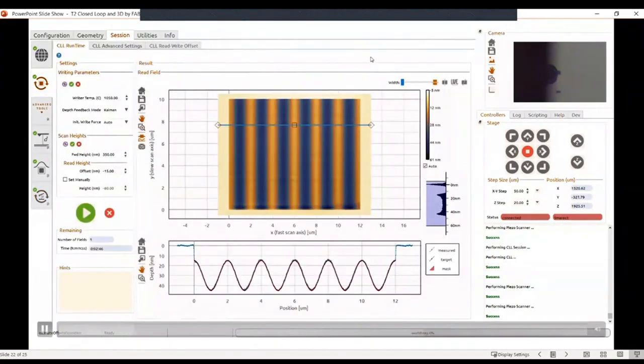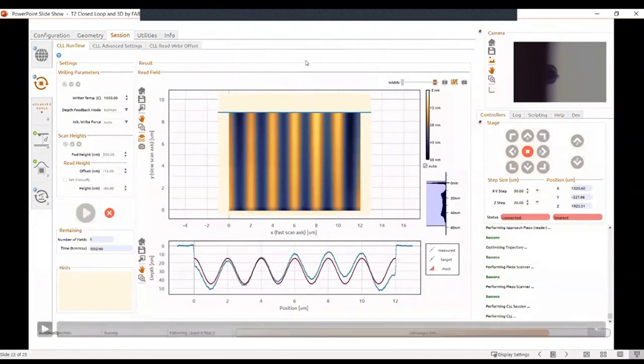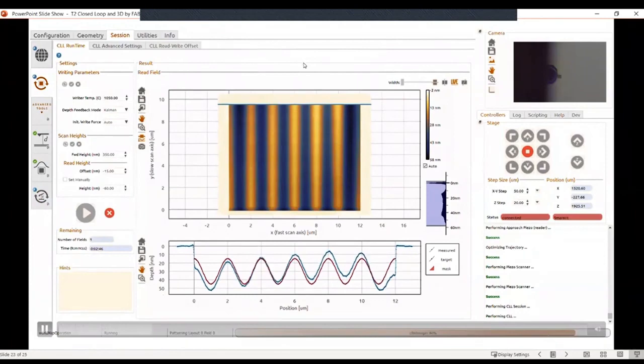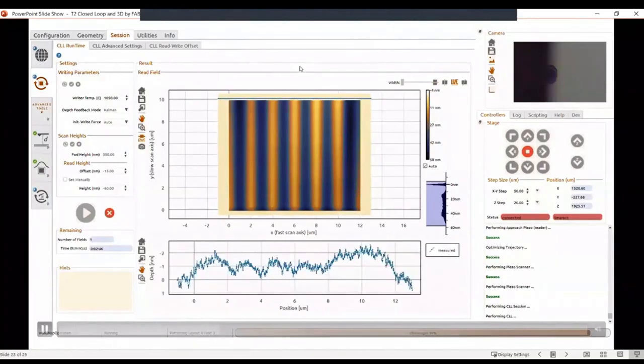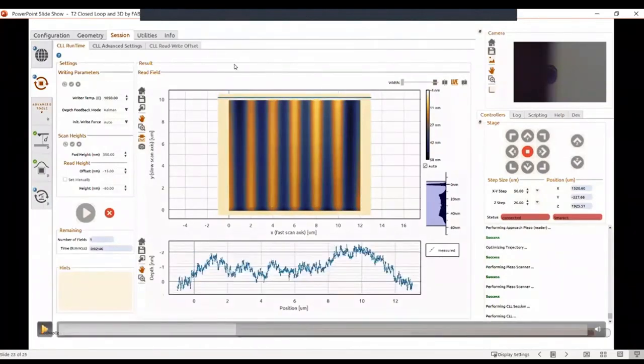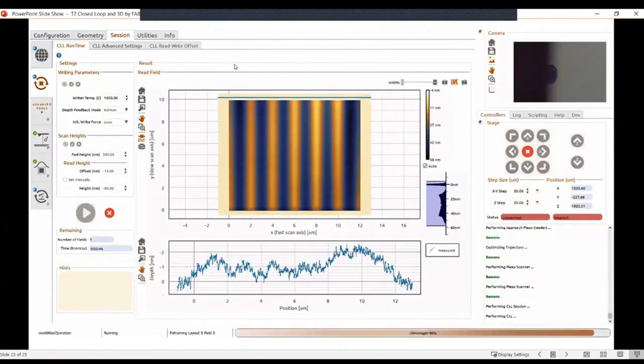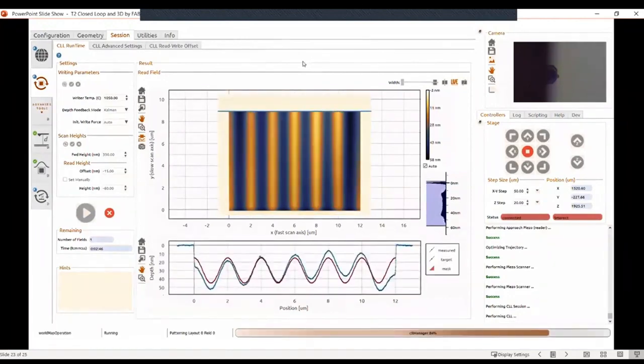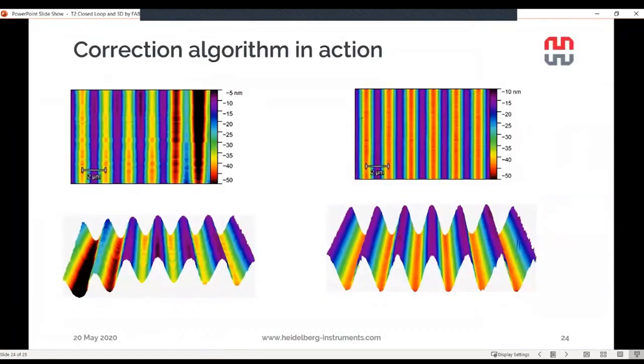Now, when we try to write the same pattern without the bowing correction, so it is now turned off, you can see that we end up with the bad example that I have shown before, where I really provoked a lot of bowing. We cannot really accurately reproduce the pattern that we want to write without the correction. But don't worry, if you activate the correction in the software, the machine will learn also this bowing effect for you and correct it accordingly. Here you see a comparison. This is the pattern that we write without the correction, and on the right you see it with the correction, and then it is actually reproduced as good as the machine can, essentially, with its intrinsic noise.